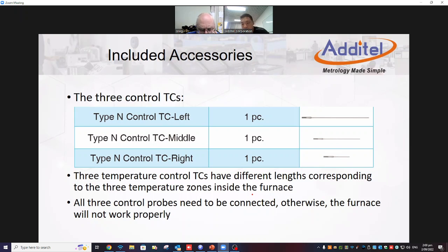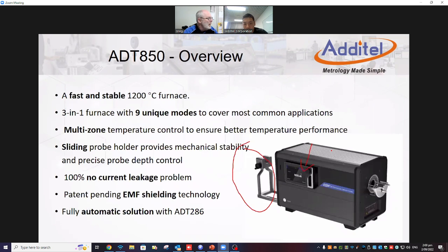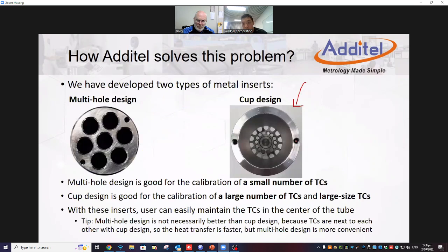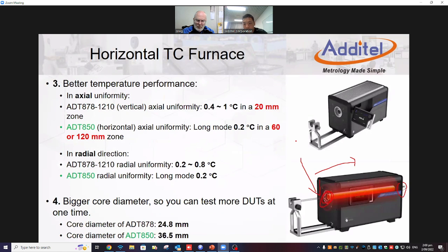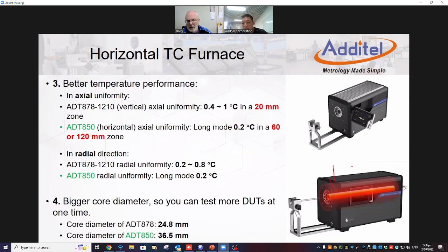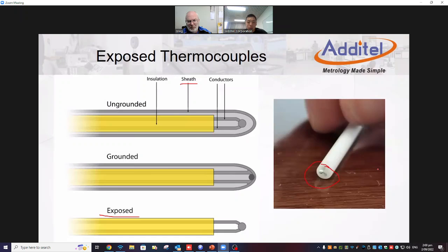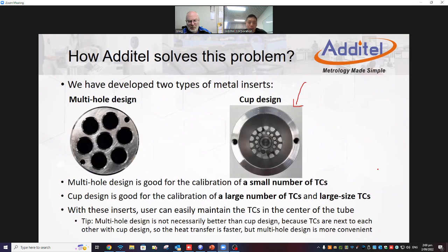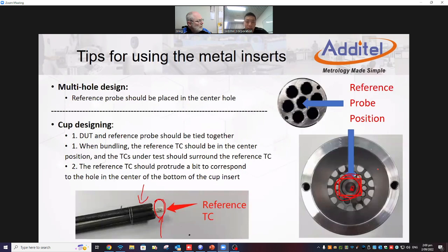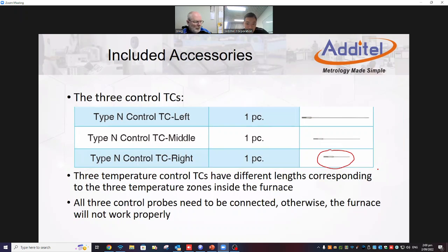The 3 thermocouples have different lengths because the furnace is pretty long, so we have divided the heating zone into 3 zones. Yes, I saw that on something else. Yeah, left side, middle, and right side. So the 3 probes are definitely for the 3 zones. And after that, we have the algorithm to optimize the heating and cooling, and also the entire temperature field. So this is the thermocouple.